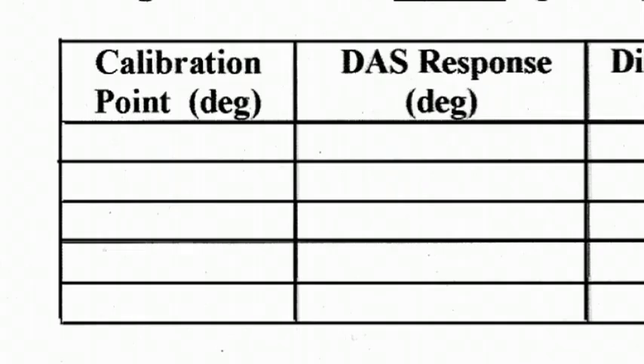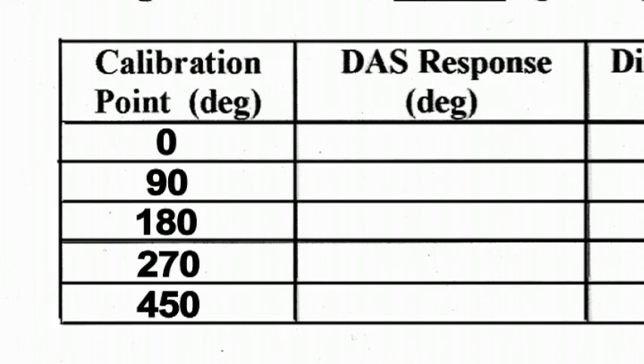In the first column, labeled calibration point degrees, record the alignment of the instrument boom that we determined using the GPS unit. In the second row, record the value, which is 90 degrees, plus the value determined for the instrument boom. In the third row, add an additional 90 degrees until the table is filled in. These values will be our reference values for the calibration.